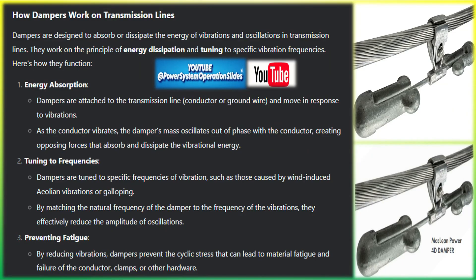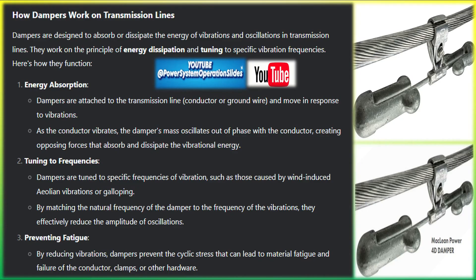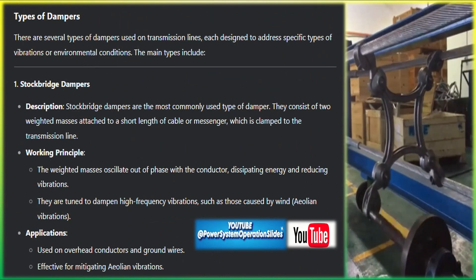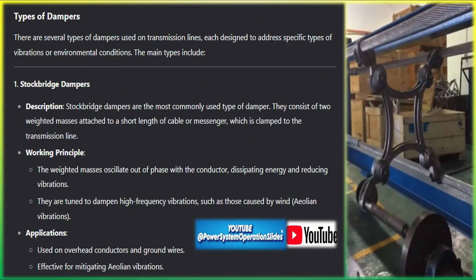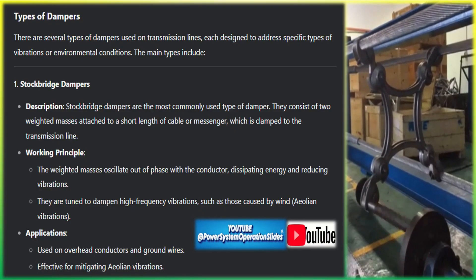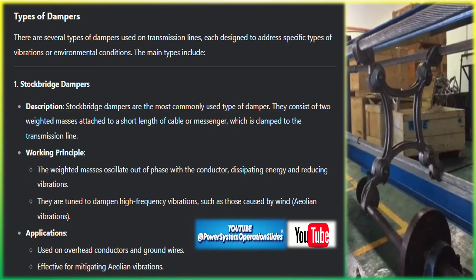Before discussing dampers, it's important to understand the various types of vibrations that occur in overhead transmission lines. Aeolian vibration is caused by low-speed, steady winds between 2 to 12 meters per second flowing perpendicular to the transmission line. As wind flows past the cylindrical surface of the conductor, it causes alternating vortex shedding, which leads to conductor vibration.